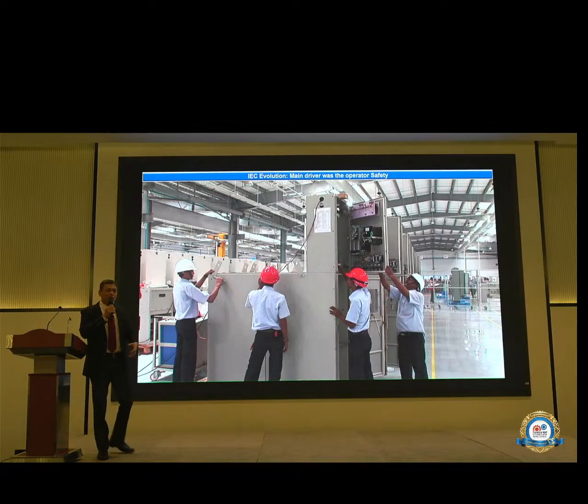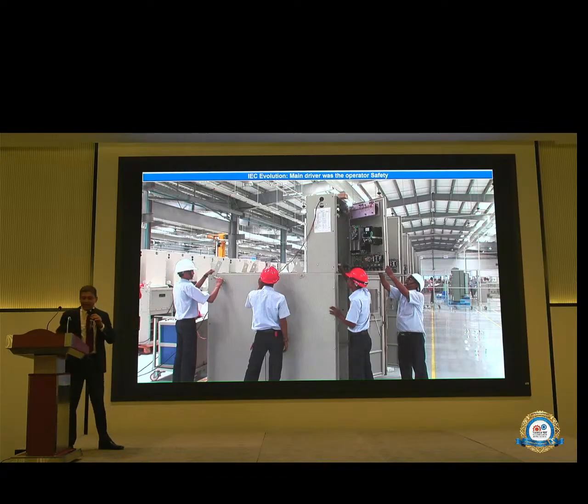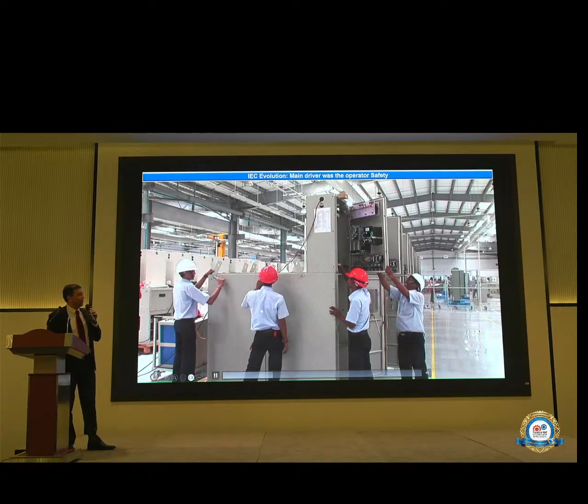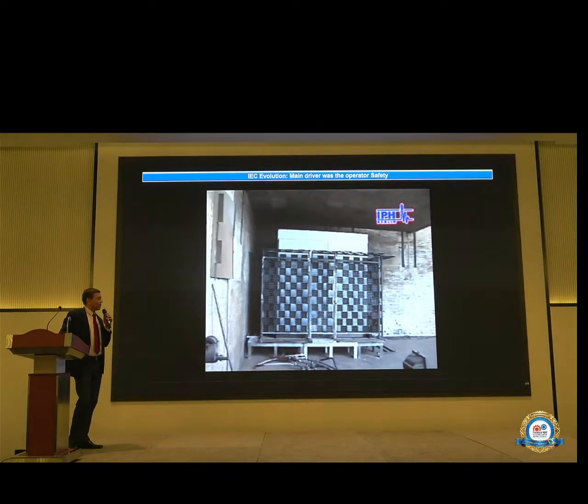The vacuum was used for applying brakes in old trains. What happens, you see in cowboy movies, they cut the vacuum, then what happens? The train cannot stop. If you keep the brake open using vacuum, now if somebody cuts the vacuum, the brake will fall on the wheel and stop the train. So this became fail-safe. In the same way, in switchgears, look. The impact of the failure is so severe that one has to see it to believe it.